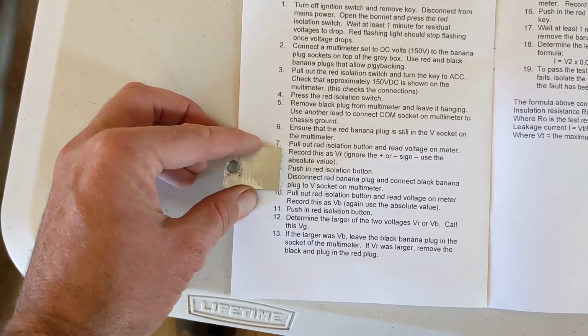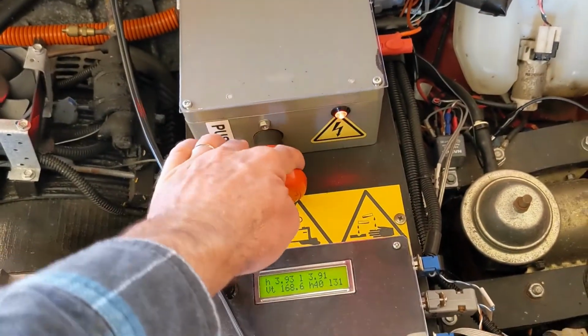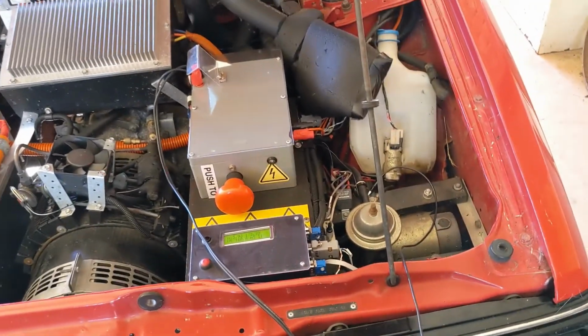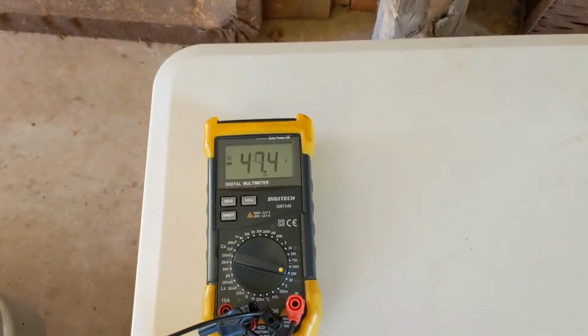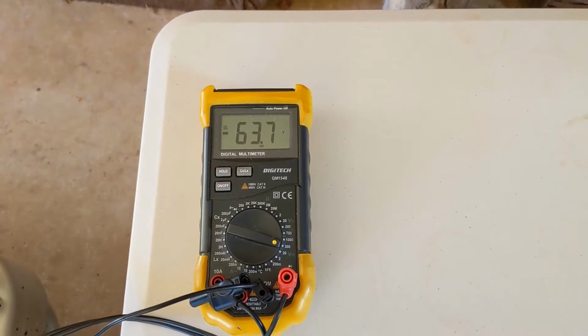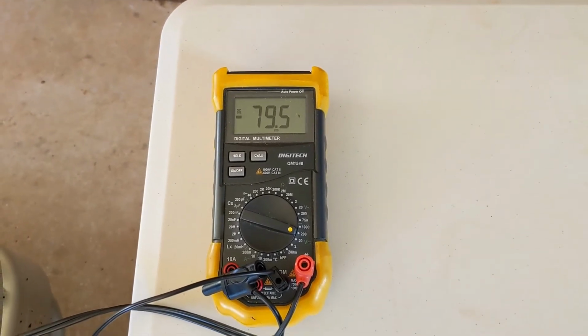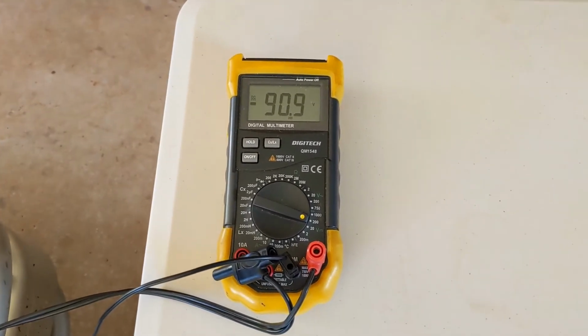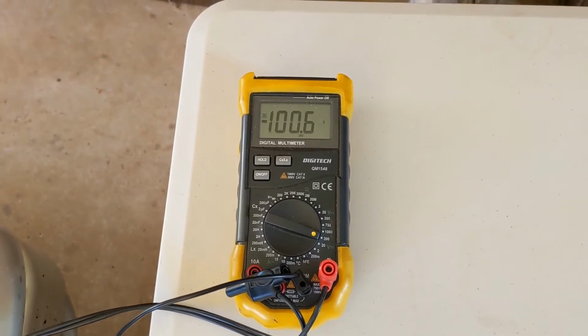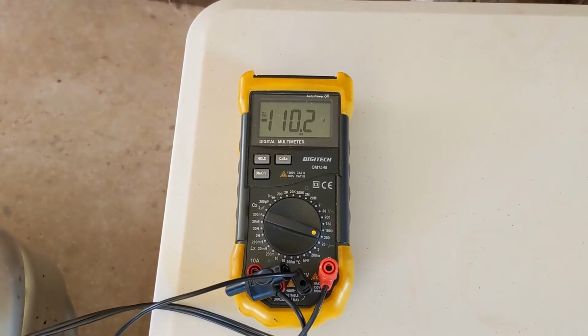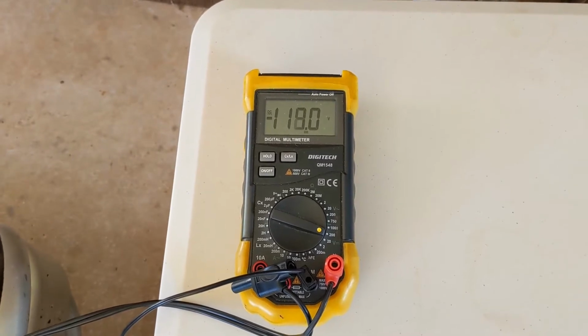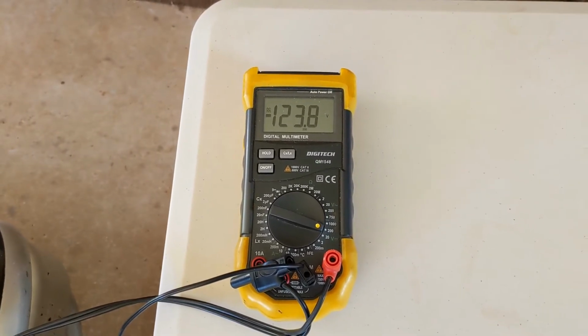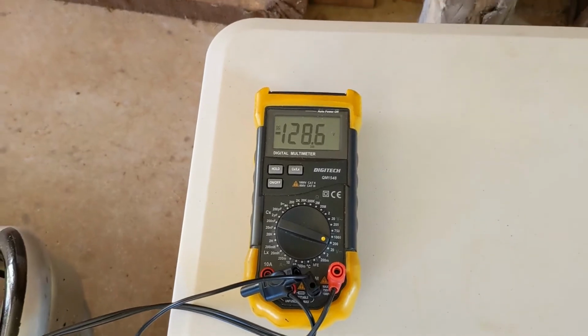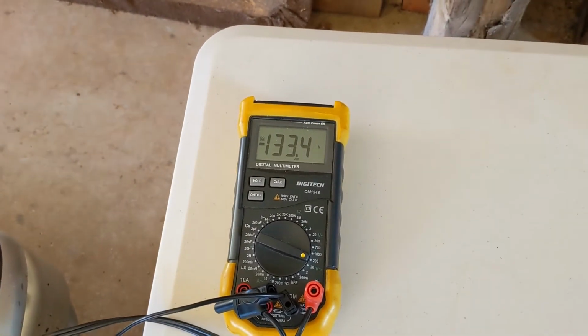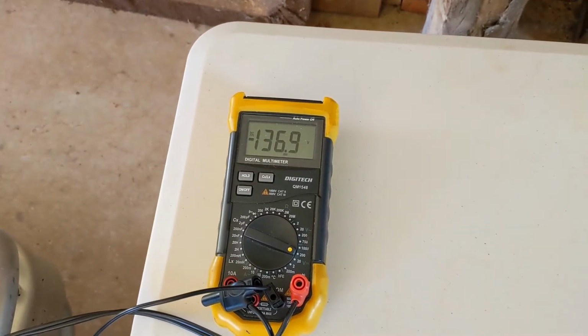Next is step 7: pull out the red isolation button. The voltage comes back up, and we read it on the meter. This takes a while because of capacitors and other components in the circuit, so I wait until it's reasonably stable. It's not critical to leave it a long time, just until it's reasonably stable.